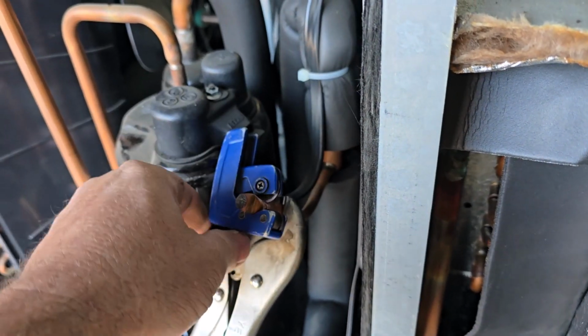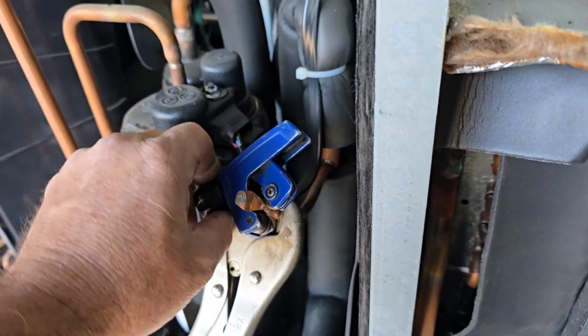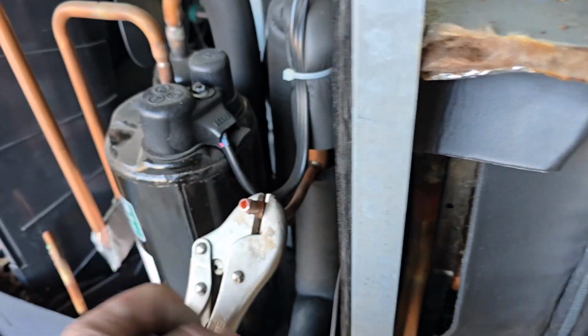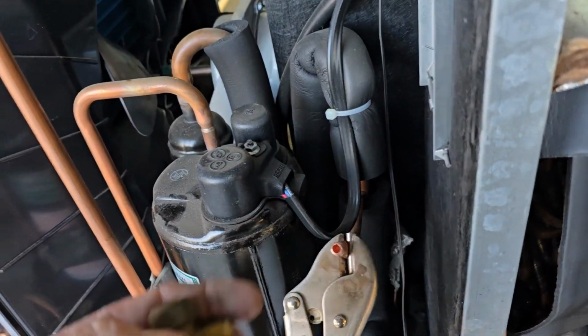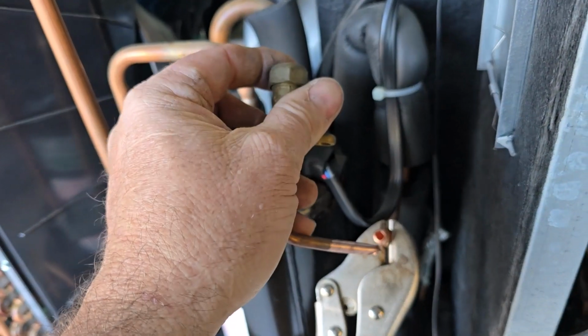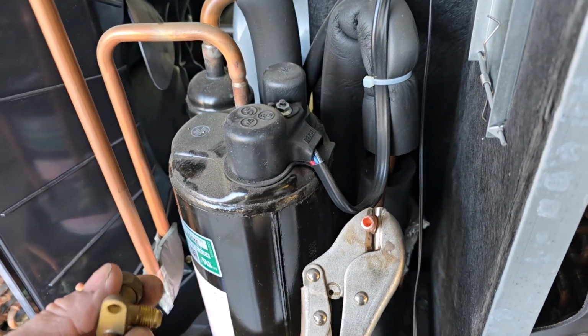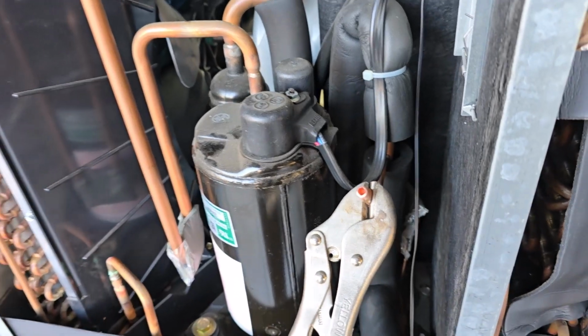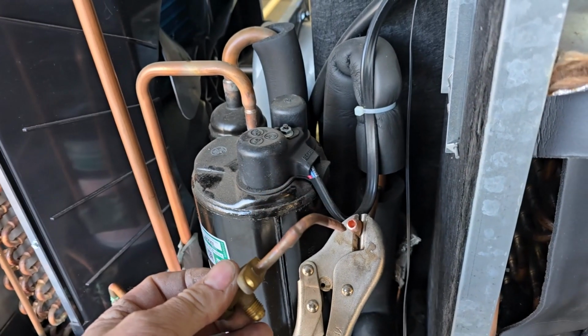See, that little quick psh, and that's all it did. And even if it leaked just a tiny, tiny bit, as long as the valve you're going to add has the core out, I'm going to use this valve with it open, you could put it in there and it's not going to have any issues, because it won't be building up pressure. It'll give you time to braze it.